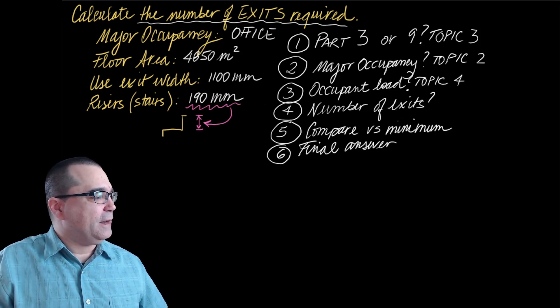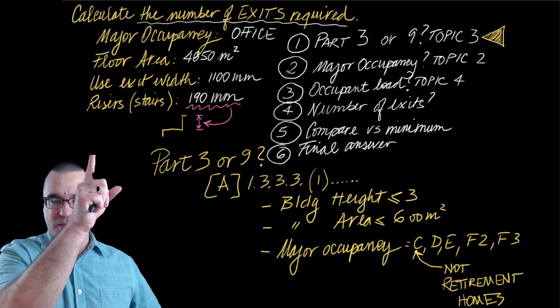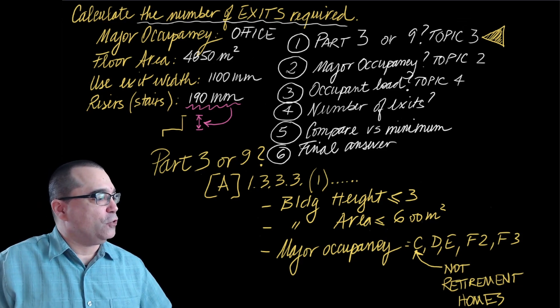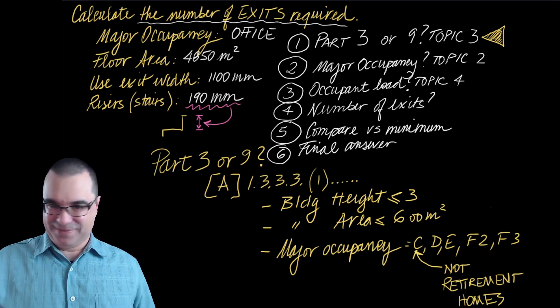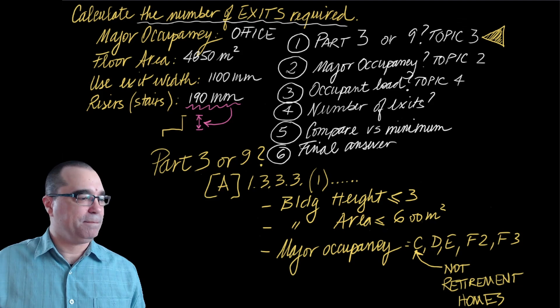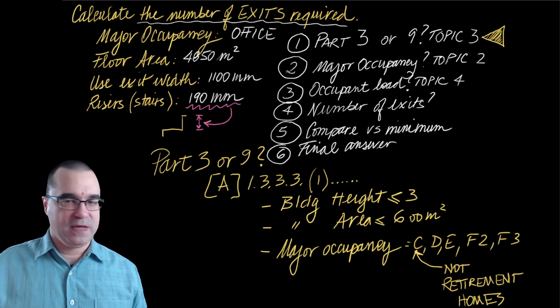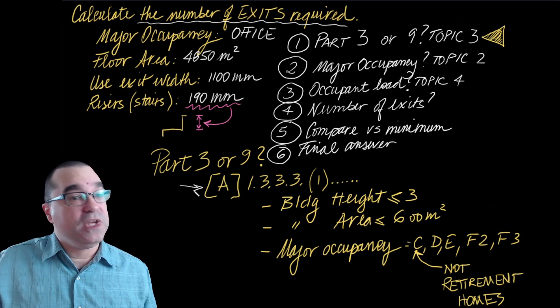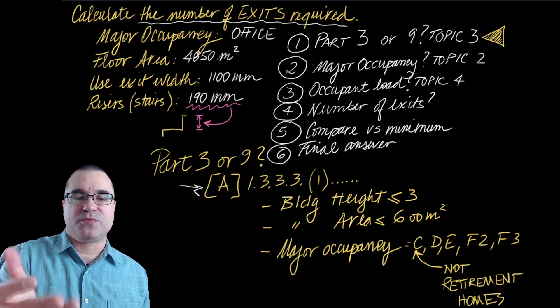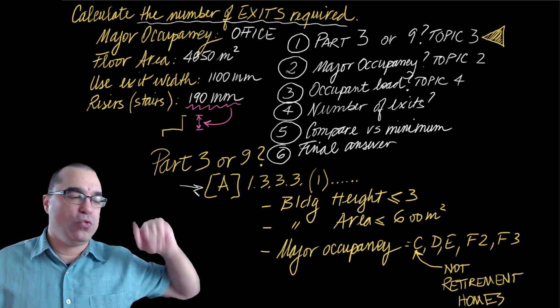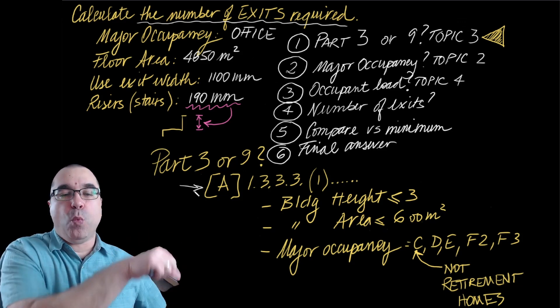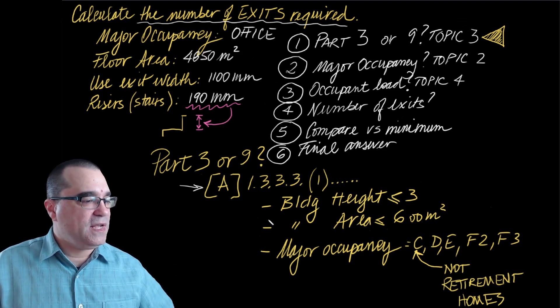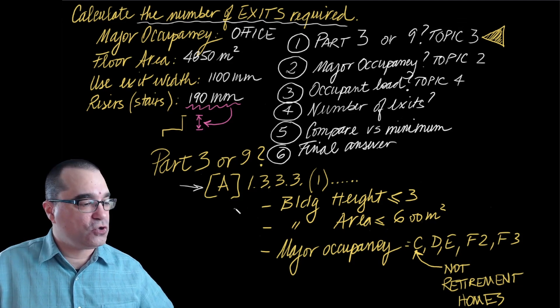Let's start with step number one, which is determining whether or not this building, or at least the floor area that we're identifying, is covered under part three or part nine of the Ontario building code, because that tells us then where to find all relevant information to solve this question. To figure out whether a building is part three or part nine, the best way that I recommend doing this is to use the requirement under sentence 1.3.3.1. That's 1.3.3.3.1, which gives you three conditions to identify a part nine building. If even one of these three conditions fails, automatically, not a part nine, it's a part three building.